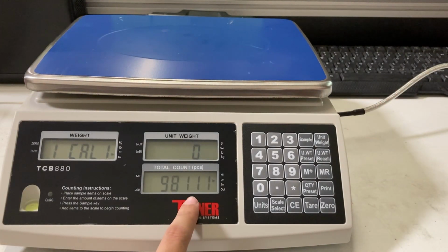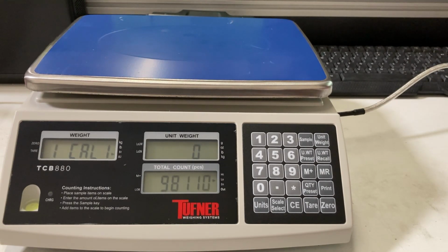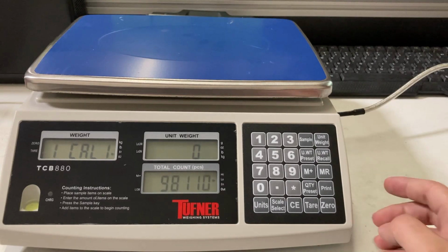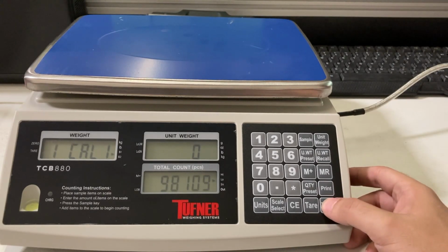It's 0, not fluctuating too much - that just depends on the current count of whatever scale it's connected to. So at 1 cal 1, make sure the scale is empty, because we're doing the 0 calibration with no weight on there. So what you're going to do is press 0.